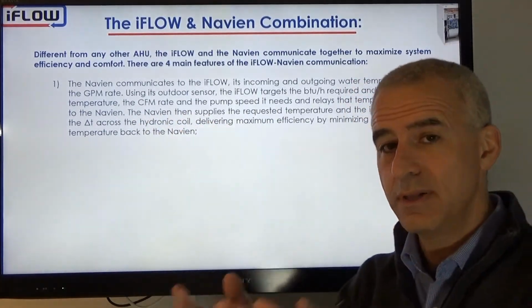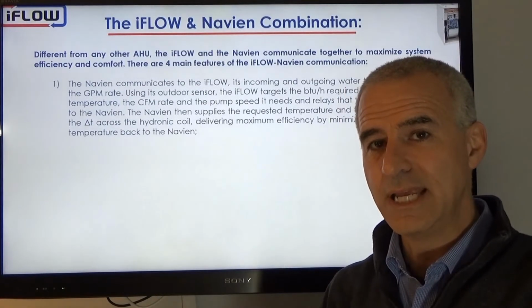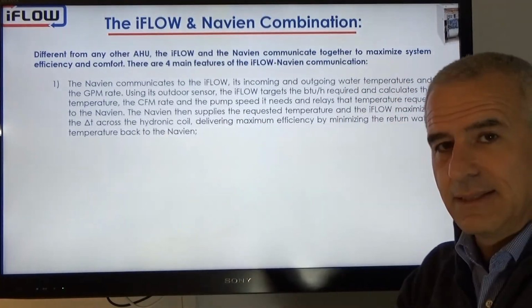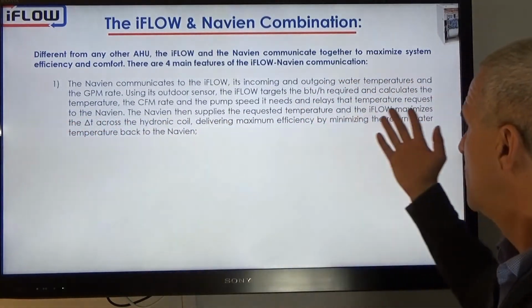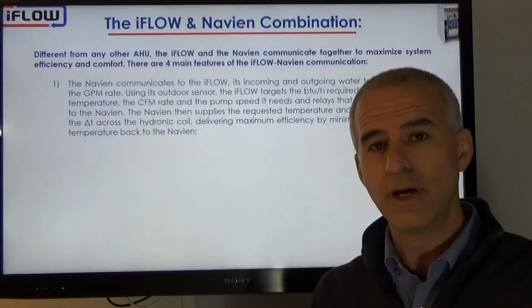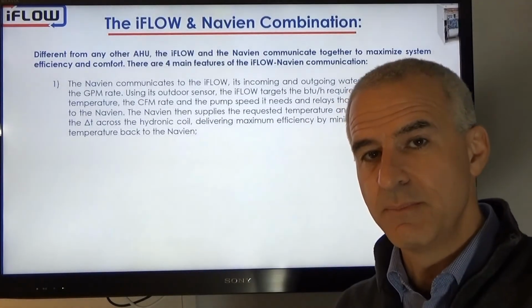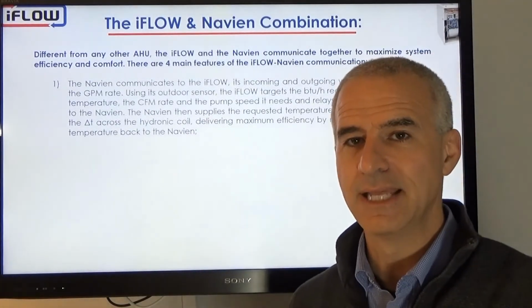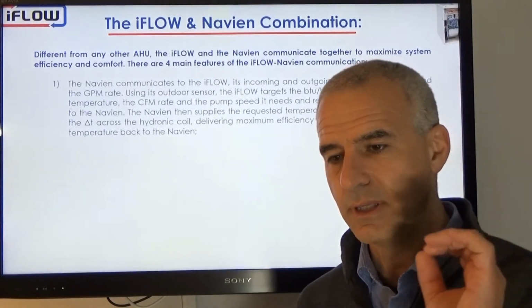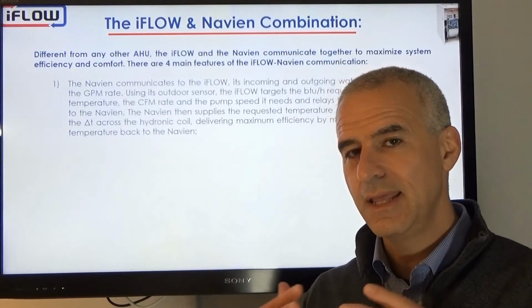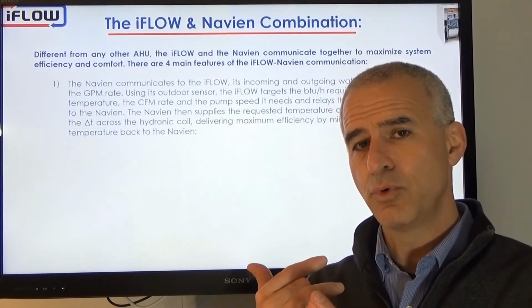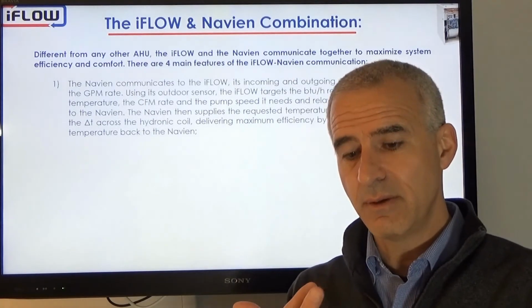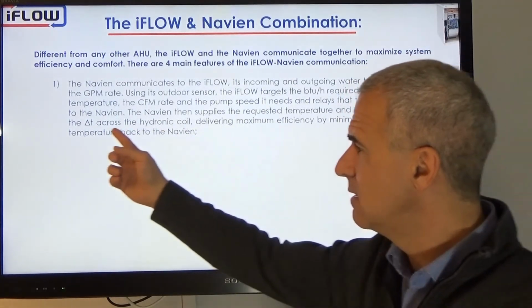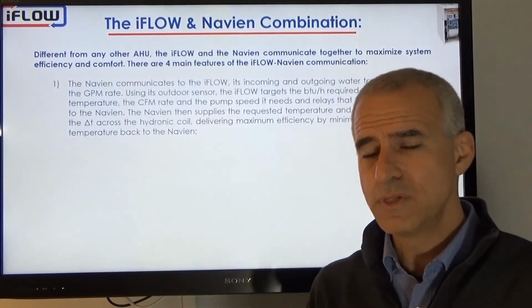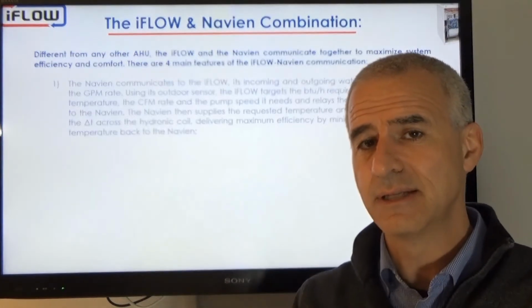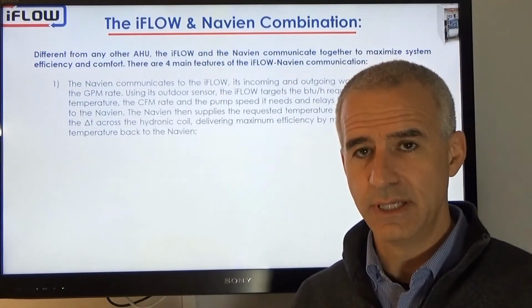The Navien then responds to that request, sends us the temperature we need into the iFLOW, and then we modulate the system to maximize the delta T across the hydronic coil, which delivers the lowest return temperature back to the Navien so it can fully condense. So not only are we delivering the exact BTUs, we are communicating and coordinating on the supply temperature into the primary loop, the CFM rate, GPM rate, and the delta T across the coil, and most of the time we're getting between 45 and 60 degree delta T's across the coil, which is unheard of in the industry.